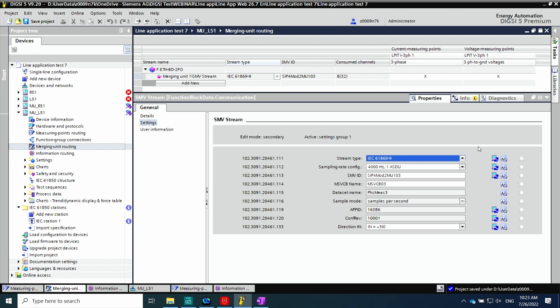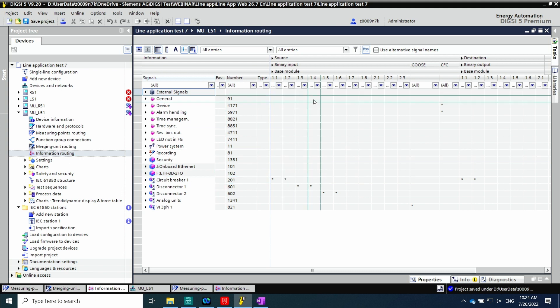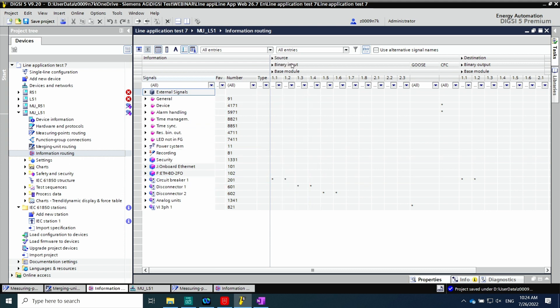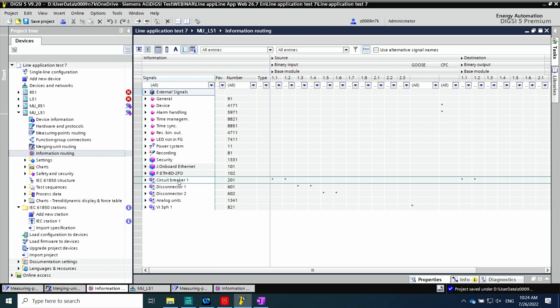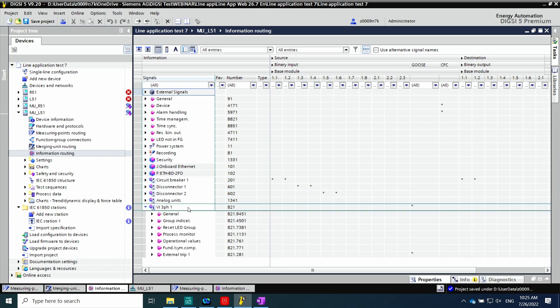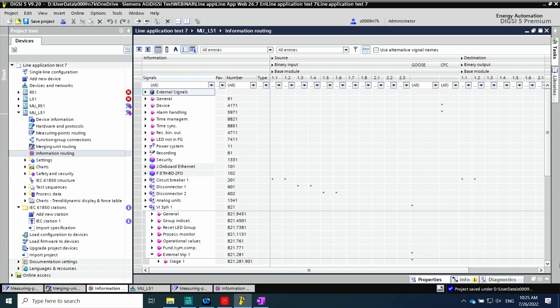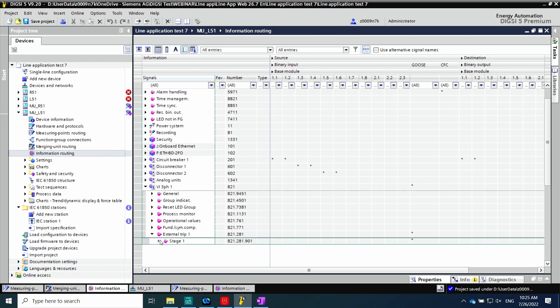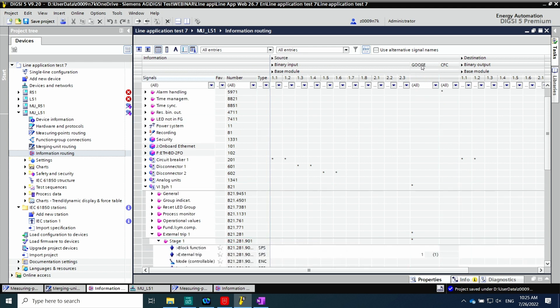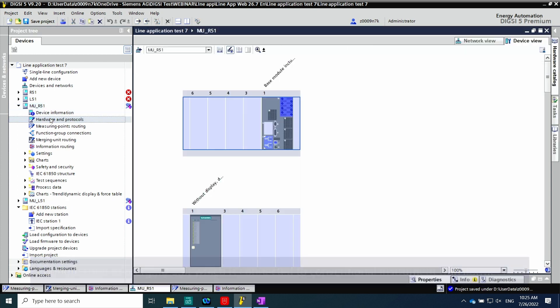For binary information transfer, the GOOSE application described in IEC 61850-7-2 is used. It is possible to transmit the position of the circuit breaker, position of the disconnector, and so on. In this merging unit, the binary inputs are acquiring the position of circuit breaker 1 and the positions of disconnectors 1 and 2. In the group voltage and current, the function external trip is available. The external trip functionality permits receiving the signal from the protection device to trip the circuit breaker. For merging unit R51, which receives information from conventional current transformers, you can see in hardware and protocols the inputs for the current transformers and voltage transformers.